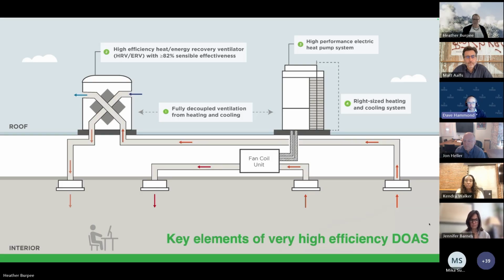The second component is that ERV/HRV, energy or heat recovery ventilator, operating at greater than or equal to 82% sensible effectiveness. The third component is making sure the heating and cooling system is a high performing electric heat pump system. The fourth is right-sizing, making sure that system is sized appropriately for the space and fully accounts for the benefits of the ERV/HRV, reducing the ventilation load so you're not oversizing and spending energy unnecessarily.